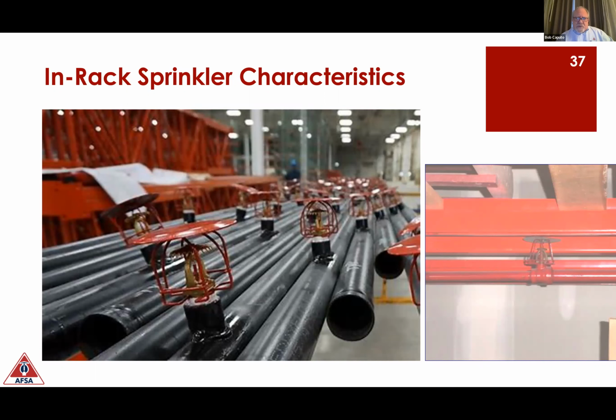I mentioned in-rack sprinklers. This is what that pipe looks like before it goes into the racks. And here are these little, I referred to Bambi as the head guard on the sprinkler. When you see these in the racks, you see these water shields on top. You see these little caps here, if you will. These are not heat collectors. What these are doing is shielding the sprinkler from the water droplets that might fall on it from above, from the ceiling sprinklers. Because if you get even a drop of water on the seat of the sprinkler, it's going to act as a heat sink and delay the activation of this sprinkler until that water droplet or pool of water on this little cap here evaporates. So you don't want that delay. So it's not uncommon to have in-rack sprinklers, even when you have ESFR sprinklers.